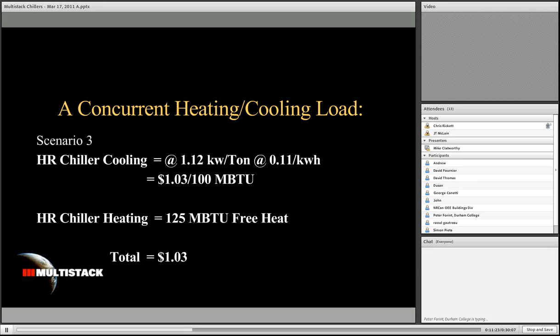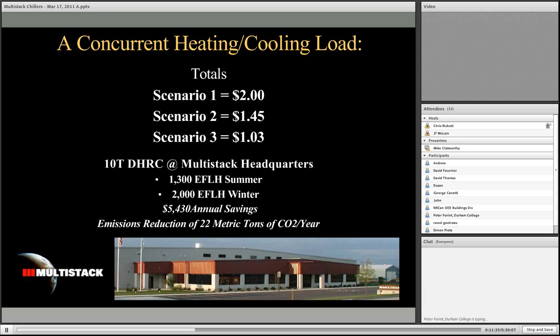The cooling component of it was $1.03 as the result of 1.1 kW per ton at 11 cents per kilowatt hour blended rate. My heat recovery, the heating side, is giving me 125,000 BTUs of free heat. So my cost is $1.03. So if we just compare those, you can see that scenario one, conventional, is $2, scenario two, which would be economizer cooling, is $1.45, and scenario three with a dedicated heat recovery chiller, it's much cheaper.